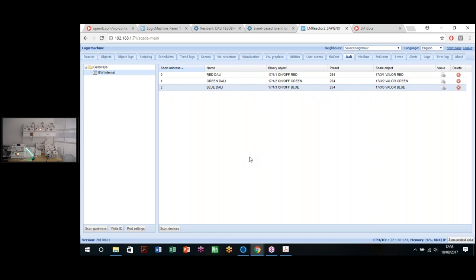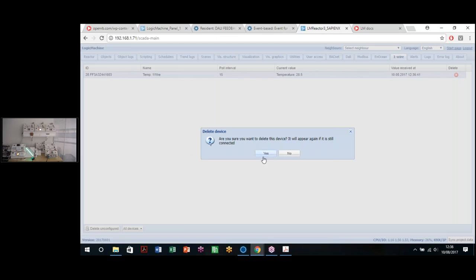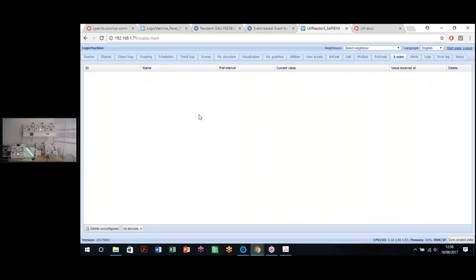This temperature probe is also very small, very cheap, of course, and we have the three cables that we're going to connect to our LogicMachine. The integration with this type of device is very easy. We just click on the one-wire tab, and in this case I'm going to delete this, I have already configured it. For the LogicMachine to obtain which devices it has connected, the only thing we need to do is connect such devices. So I disconnect and reconnect the device, so the LogicMachine knows that it has detected something, and any minute now we will see the object update in the LogicMachine.